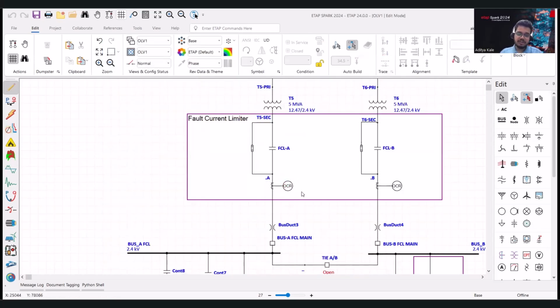So what does a trigger current limit mean? For the FCL, if the fault current exceeds that trigger level, it basically triggers the overcurrent element, which in turn opens up the contactor. Once the contactor opens up, the short circuit flows through the fuse, and the fuse rapidly melts and clears the fault.